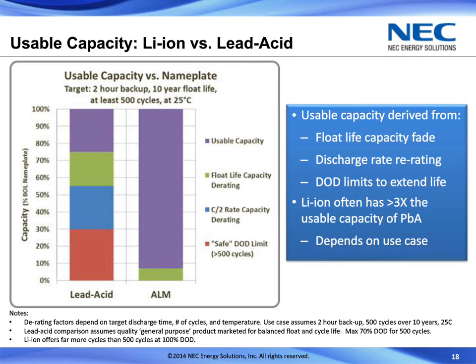In this instance, as we derate the capacity of that lead acid battery, and in all these comparisons I'm trying to use a high-quality lead acid battery that's optimized for that given application, you might see that only 30% of the stated nameplate capacity of that battery is actually usable once you derate for those factors.